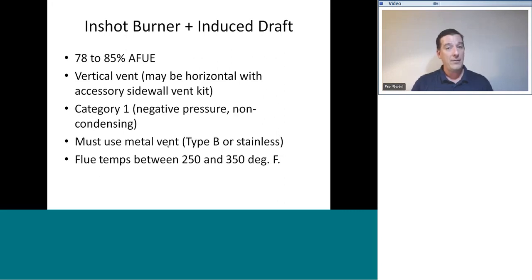It's not going to be obvious, but if you look carefully in the accessory kit information for that furnace, way in the back of the installation instructions, and if you see masonry vent kit, that's what that is. And if you're in a jurisdiction that allows that kind of thing, that can get you around having to drop a liner down the flue. And it can be a lot less expensive that way. But now you have to have that dilution air supply coming into the mechanical room as an air supply source. So be aware of that as well.